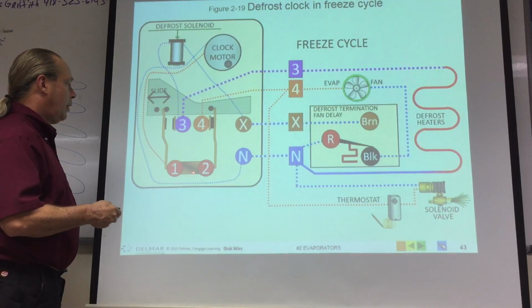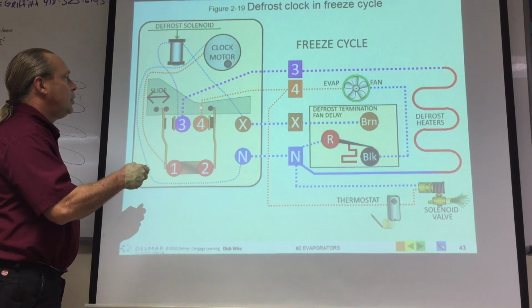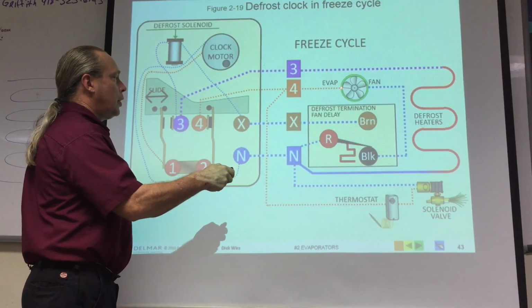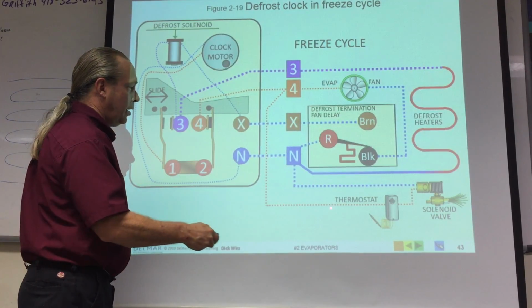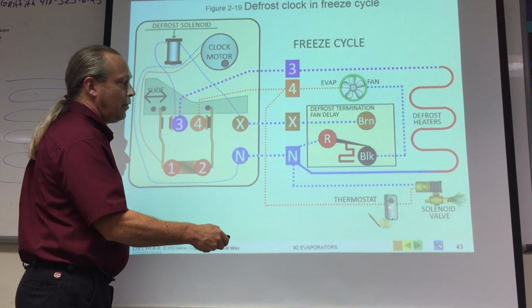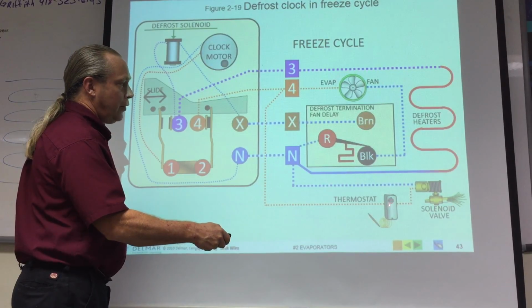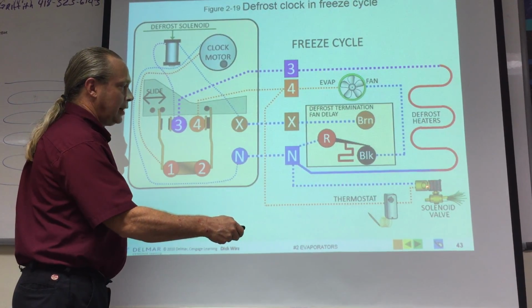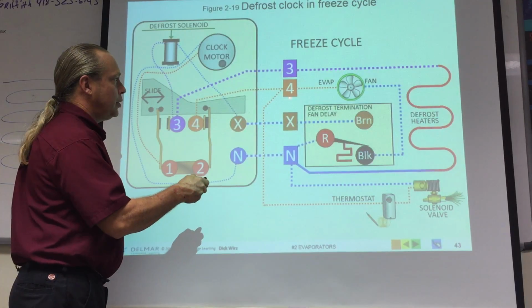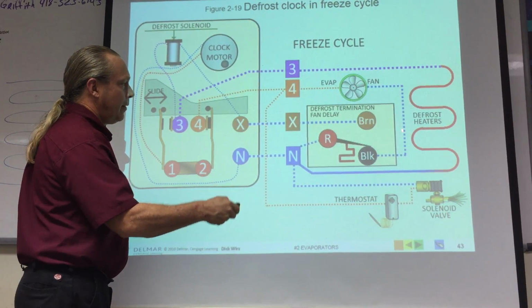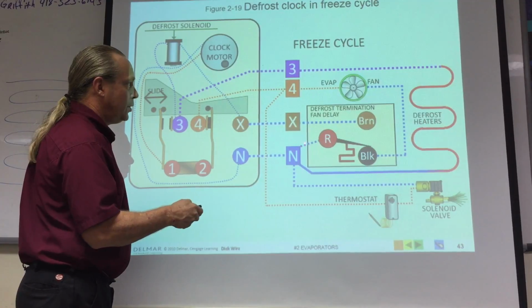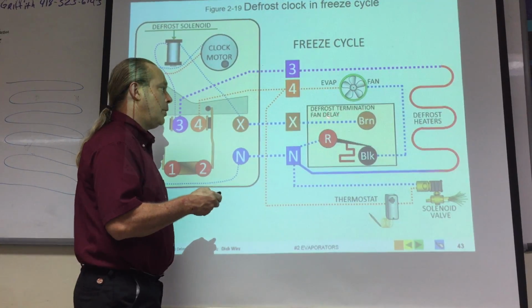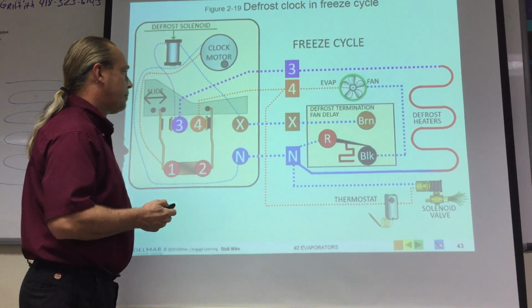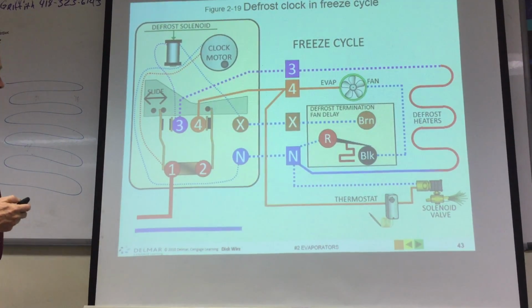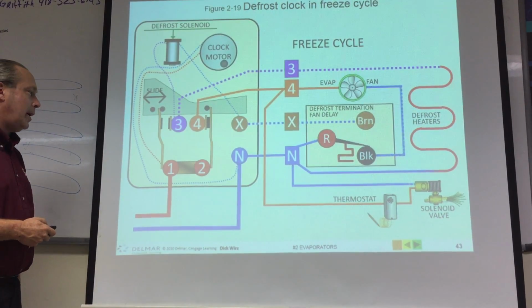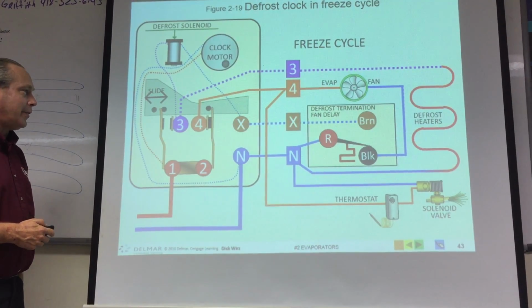So right now, power is going through 2 to 4, turning on the evaporator and providing power to the thermostat. So if the thermostat should call for cooling, that's going to activate the liquid line solenoid back to neutral. The evaporator fan and back to neutral through the defrost termination fan delay. Now they've given me my power wires. That's awfully nice of them.